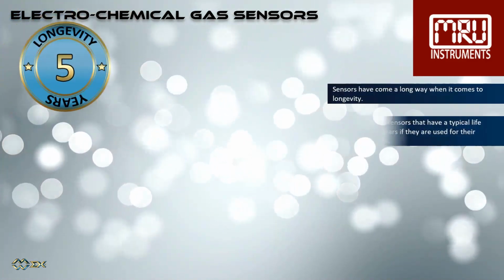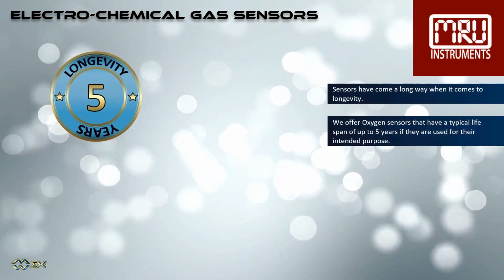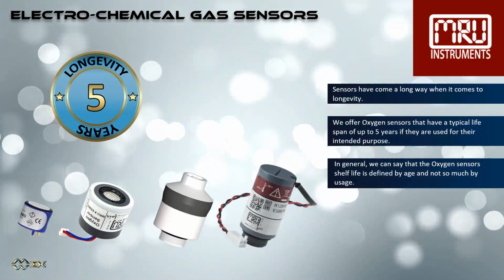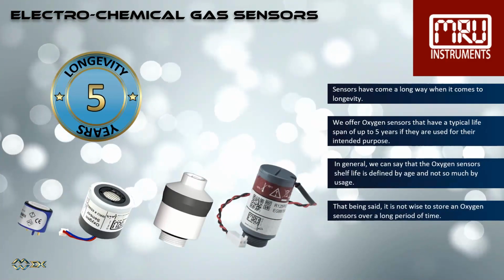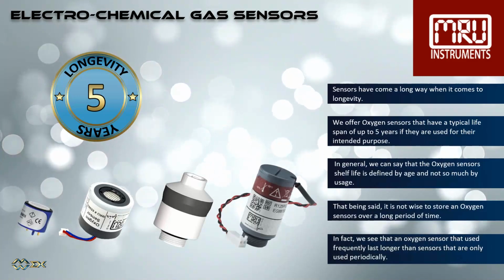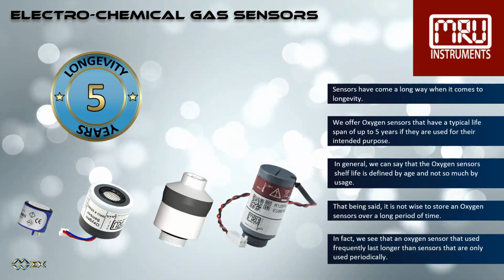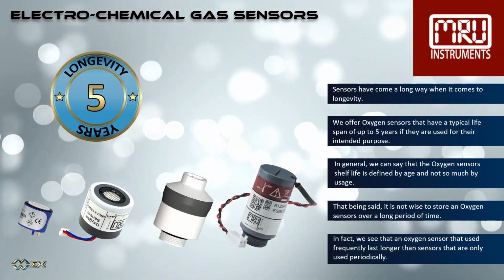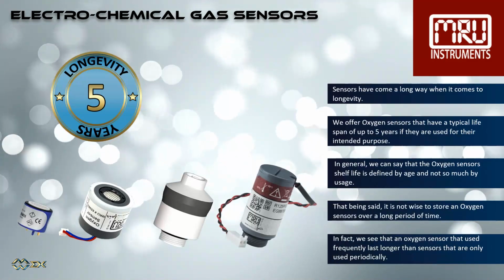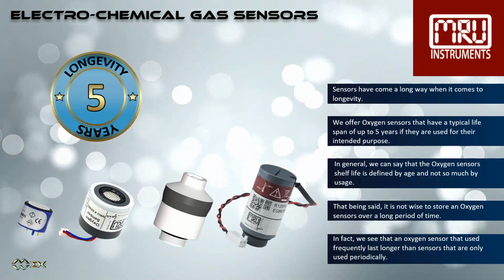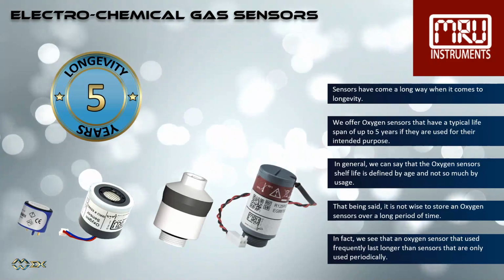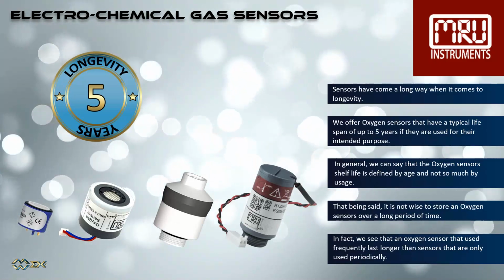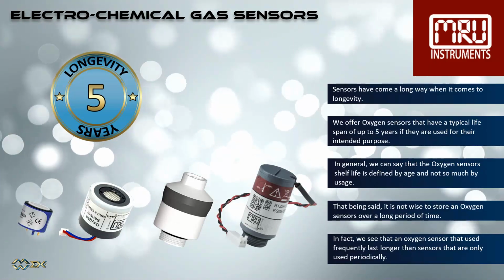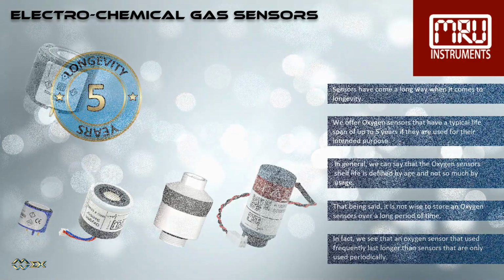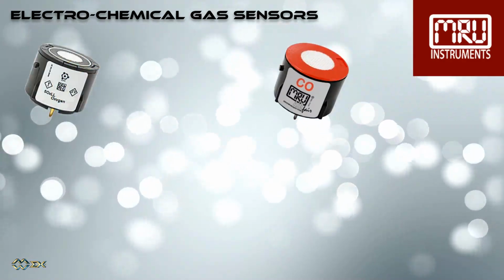Sensors have come a long way when it comes to longevity. We offer oxygen sensors that have a typical lifespan of up to 5 years if they are used for their intended purpose. In general, we can say that the oxygen sensor's shelf life is defined by age and not so much by usage. That being said, it is not wise to store an oxygen sensor over a long period of time. In fact, we see that an oxygen sensor that is used frequently lasts longer than sensors that are only used periodically. But this is only for the oxygen sensor.